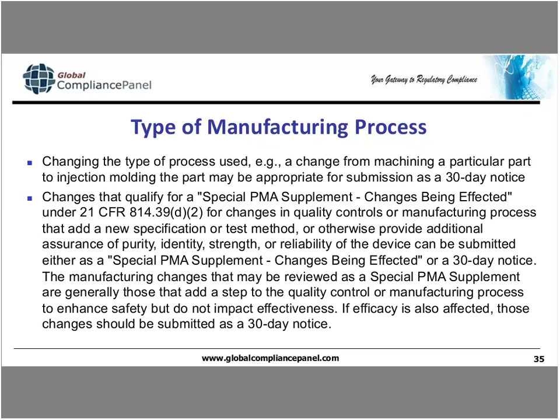Here are some examples of changes that do not qualify for submission of a 30-day notice. Any change in manufacturing needed to accommodate a change in manufacturing sterilization site of a finished device, device design or performance specifications, material specifications, or device operating software. FDA recommends that submissions for these changes be in the form of a 180-day PMA supplement or an alternative submission, for example, a real-time supplement as appropriate.